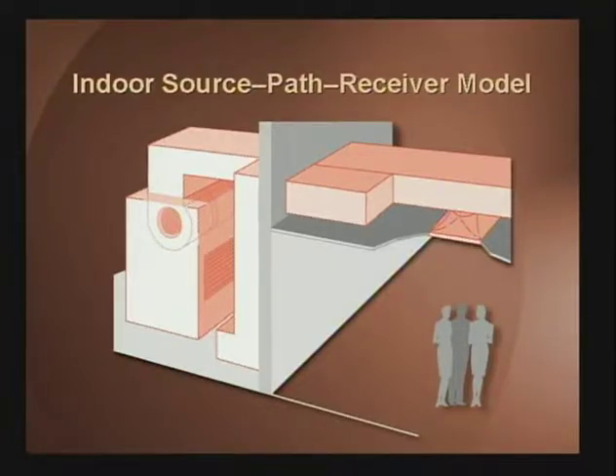You can see the fan and the equipment on the left-hand side of your screen. The supply air is ducted to the room. There will be sound that comes with that supply air through the diffuser and into the space. Part of that sound that's with that supply air will also break through the duct wall and through the ceiling tile down into the space. That's the supply breakout path.